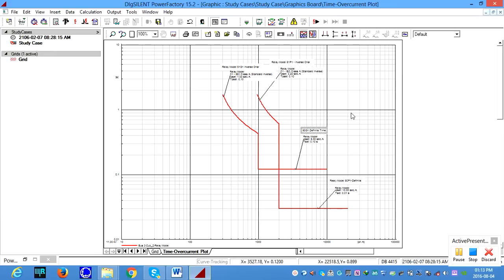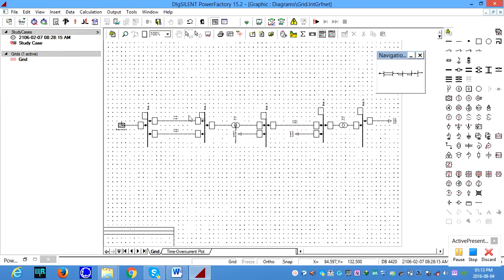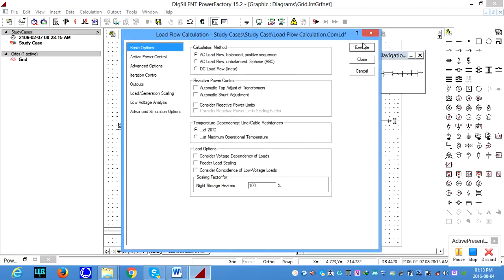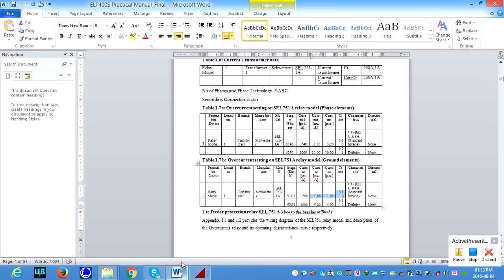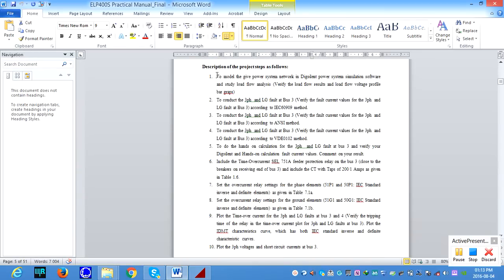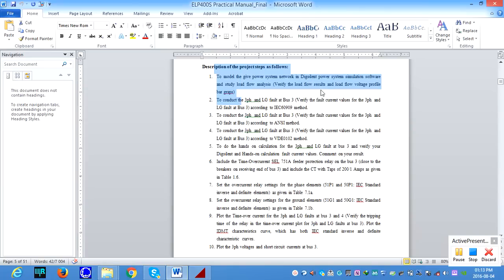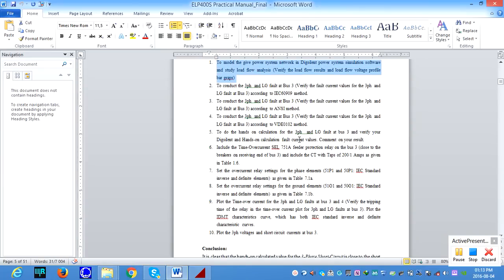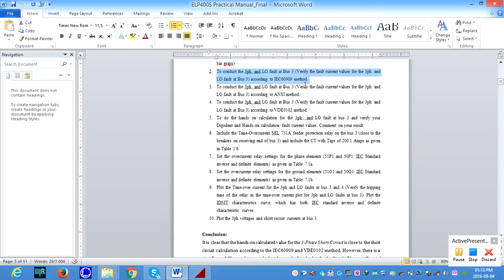Okay. Now we need to apply faults on different locations of the network to validate the protection settings. First, we make sure to conduct the load flow successfully. If you go to the manual, you see the first step is to model the network and validate the load flow results. We were happy about that. And we need to conduct three-phase and line to ground faults and verify your fault current for three-phase and line to ground faults according to different methods. Okay, I will explore the different fault calculation methods based on IEC, ANSI and VDE methods.